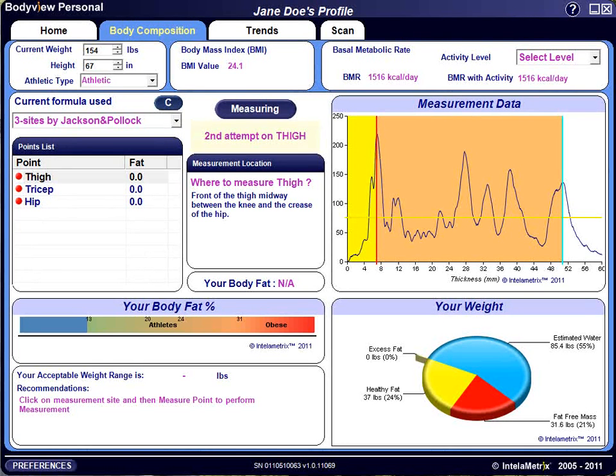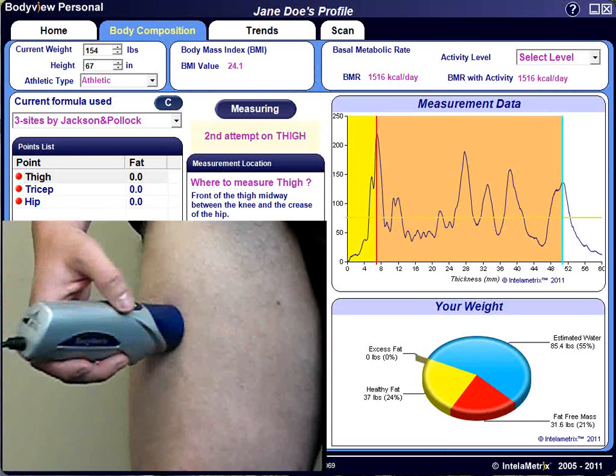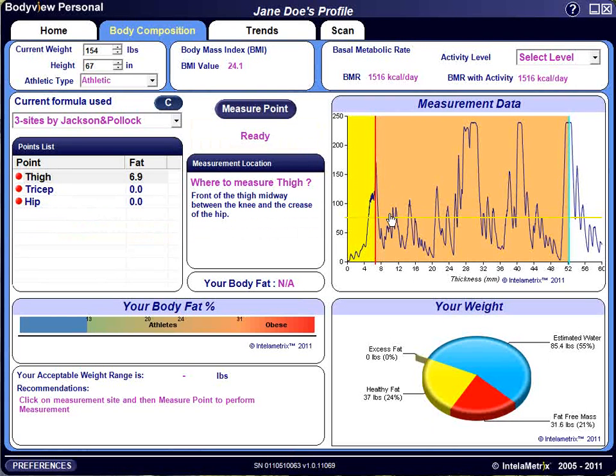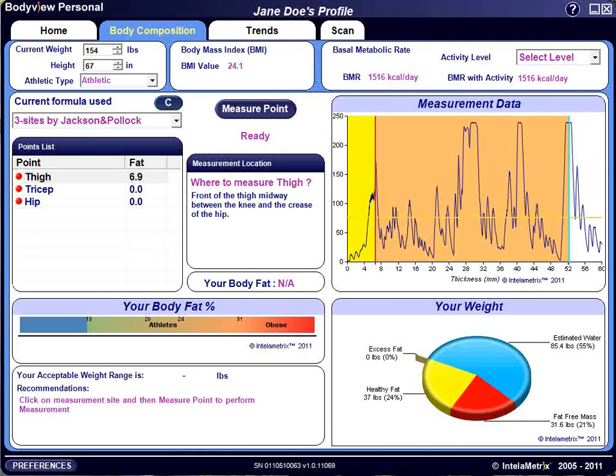The measurement data graph shows a good ultrasound signal with several clear peaks. Without using averaging, the ultrasound signal shows lots of peaks and structure. With averaging, the signal is much clearer and results in more consistent measurements overall. The software will ask you to take the measurement on the same point a second time, and if the two measurements vary by more than 10%, the software will ask you to make a third measurement. This ensures accurate readings at each location.